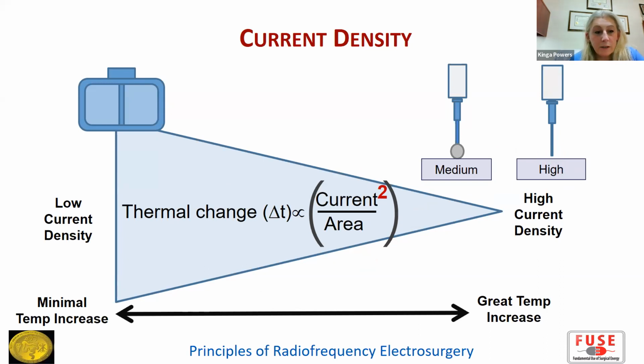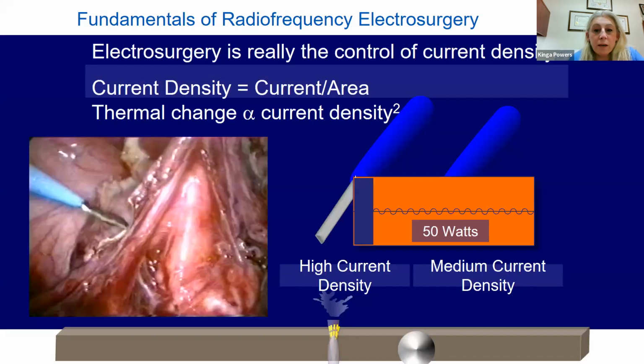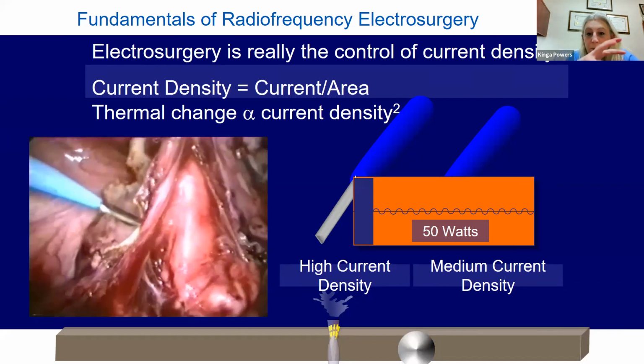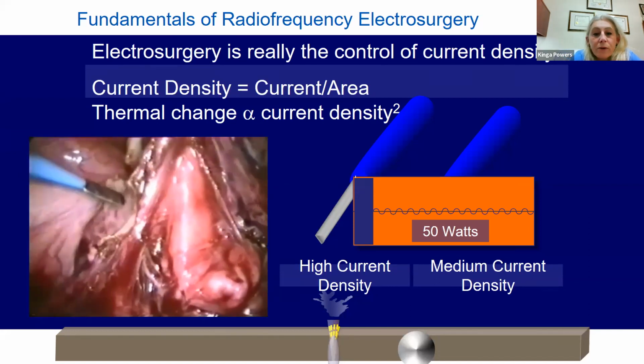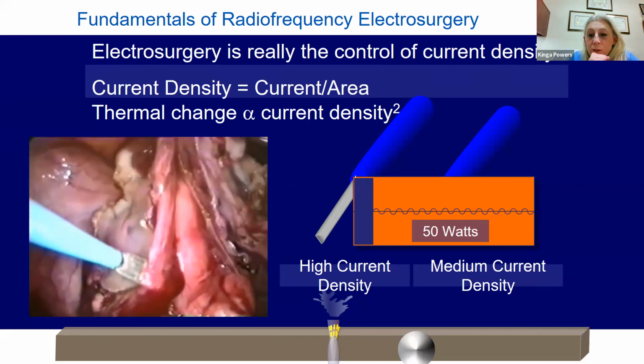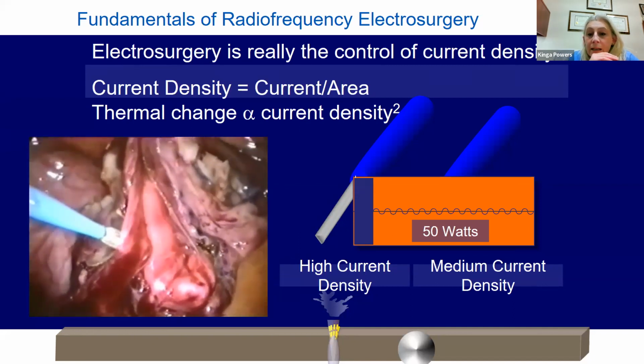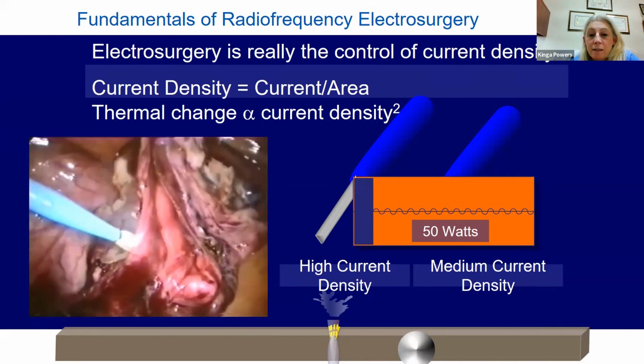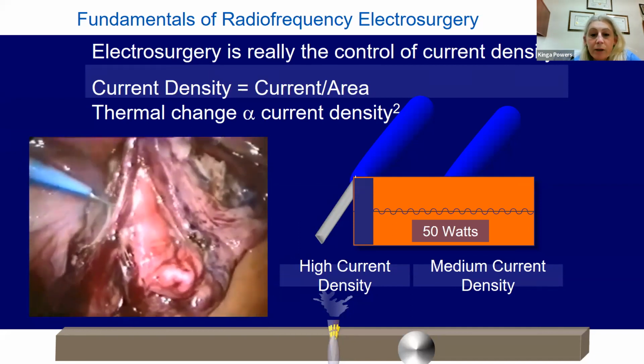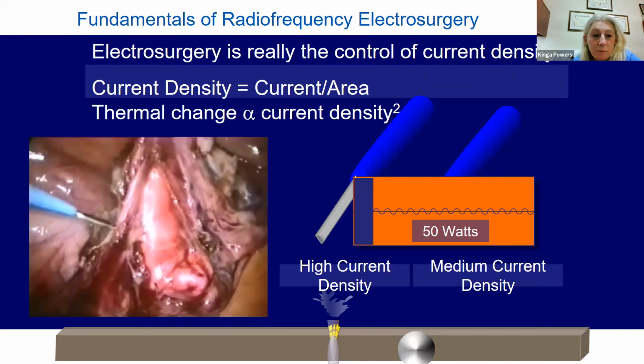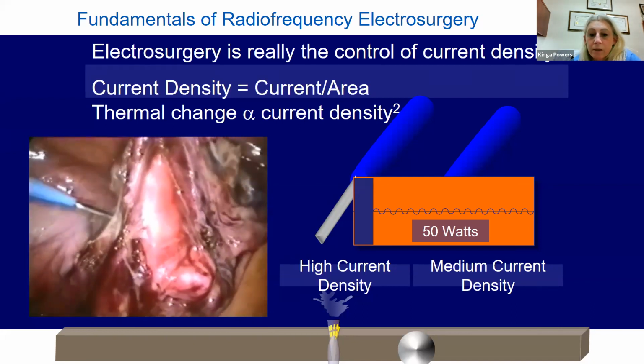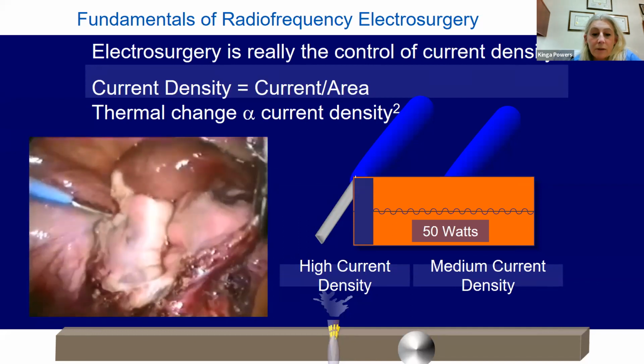If you look at the blade of your active electrode carefully: when the edge of the tip is against the tissue, you have a small surface area and high current density, which causes vaporization and results in tissue cutting. With the same setting, when the blade is flat, you get a medium current density, resulting in more desiccation and protein coagulation, since the current is spread over a wider area.